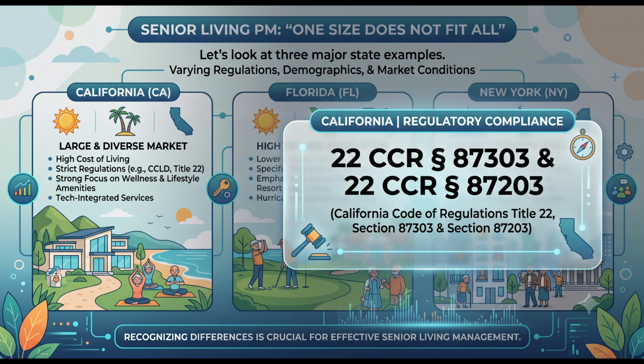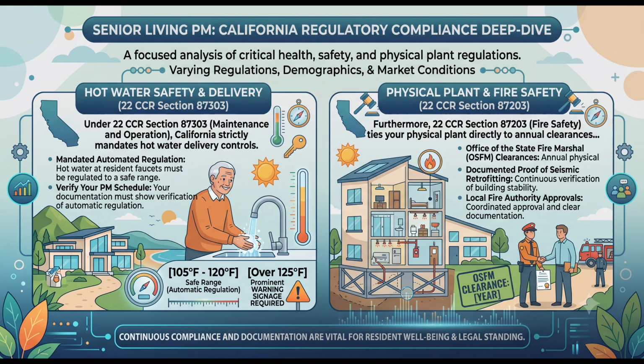First, California. Residential care facilities for the elderly, or RCFEs, are governed under Title 22 of the California Code of Regulations. Under 22 CCR, Section 87303, Maintenance and Operation, California strictly mandates hot water delivery controls. Your PM schedule must verify that hot water at resident faucets automatically regulates between 105 degrees and 120 degrees Fahrenheit. Anything over 125 degrees Fahrenheit requires prominent warning signage. Furthermore, 22 CCR, Section 87203, Fire Safety, ties your physical plant directly to annual clearances from the Office of the State Fire Marshal, OSFM, requiring continuous documented proof of seismic retrofitting and local fire authority approvals.